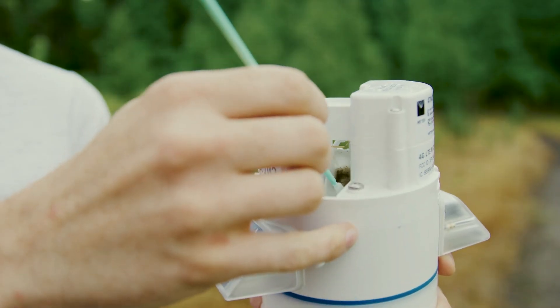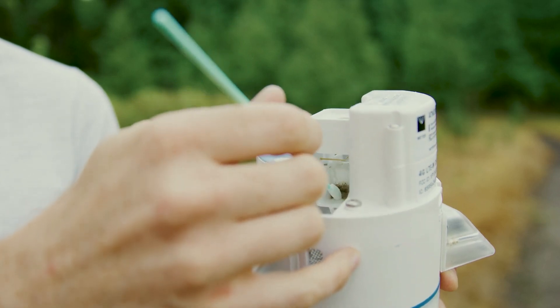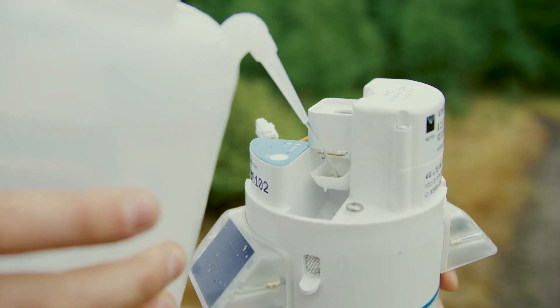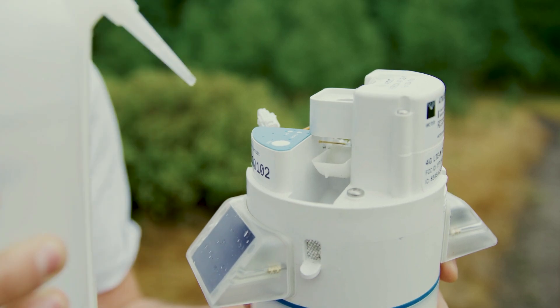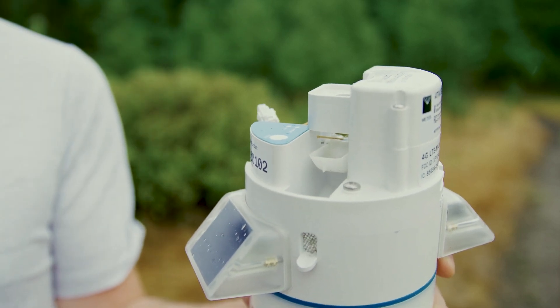Carefully clean out the tipping spoon as excessive debris buildup can throw off the calibration. Adding water can be helpful to loosen up stubborn debris but take care not to apply excessive force to the tipping spoon.